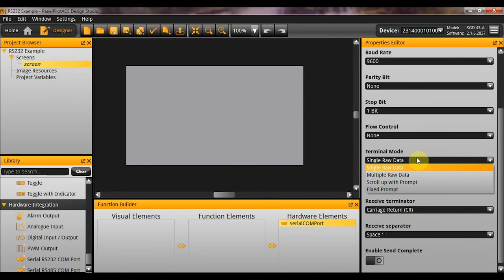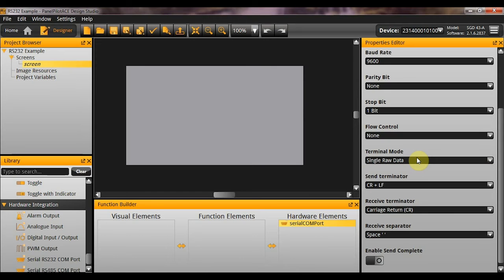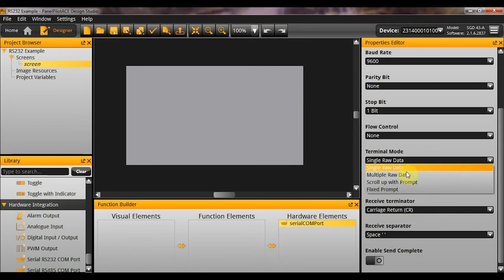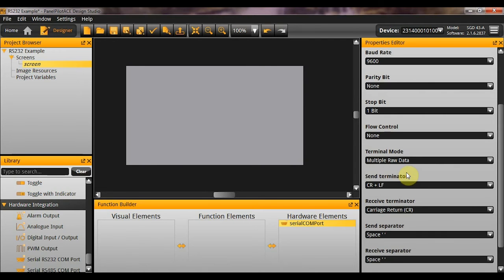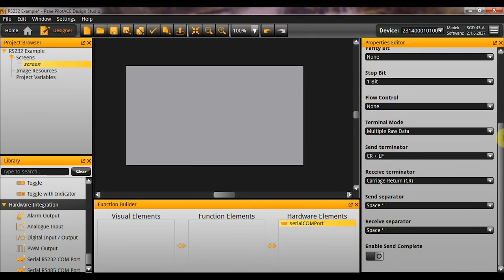Fixed prompt means that the prompt stays still. And a scroll up with prompt means that the data scrolls down the screen as it goes. I'll give you an example of those so you can see exactly what they look like when we get to that point. Single and multiple raw data basically refers to whether we're expecting more than one variable to be transmitted over the RS-232. I would normally just stick with multiple raw data unless I wanted a prompt. In which case, I prefer the fixed prompt but whatever works for you. And as I say, I'll give you an example of these later so you can actually see how they look.